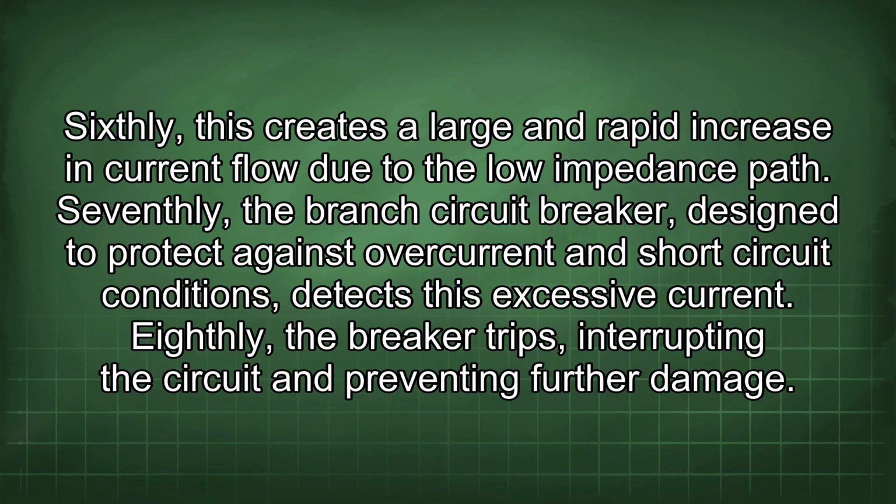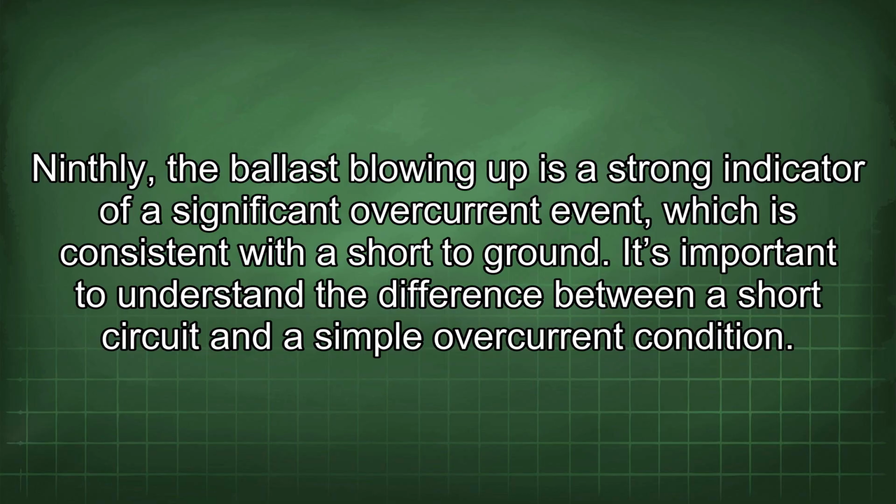Sixthly, this creates a large and rapid increase in current flow due to the low impedance path. Seventhly, the branch circuit breaker, designed to protect against overcurrent and short circuit conditions, detects this excessive current. Eighthly, the breaker trips, interrupting the circuit and preventing further damage.